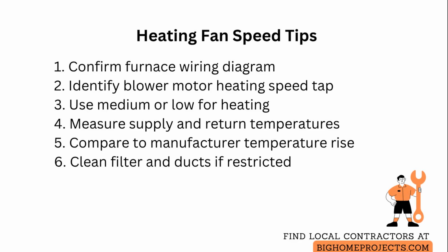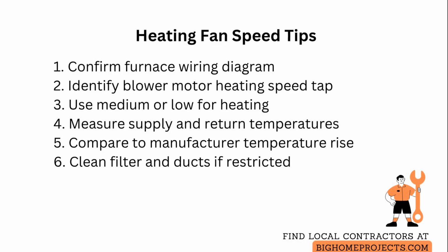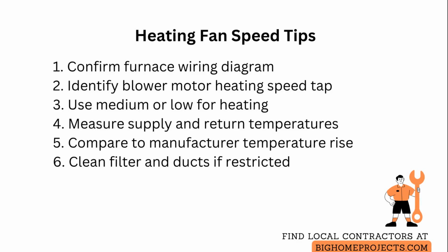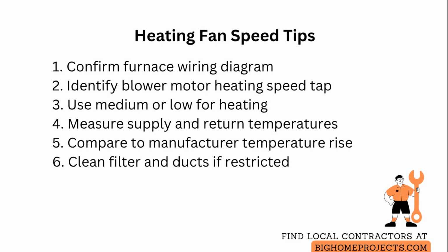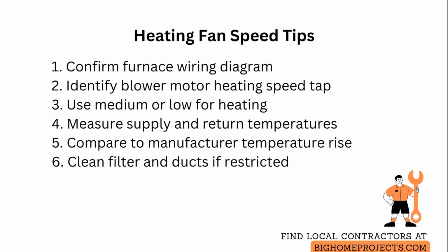Start by confirming the furnace wiring diagram to identify which fan speed tap on the blower motor corresponds to the heating function. If your blower motor has multiple speed taps, labeled high, medium, low, and a common, you will usually see the heating tap tied to a medium or low speed rather than the high speed used for cooling.